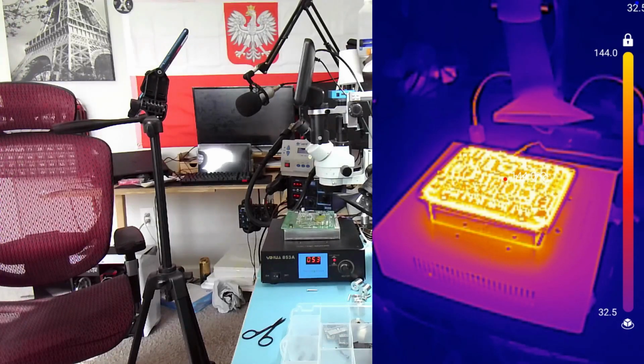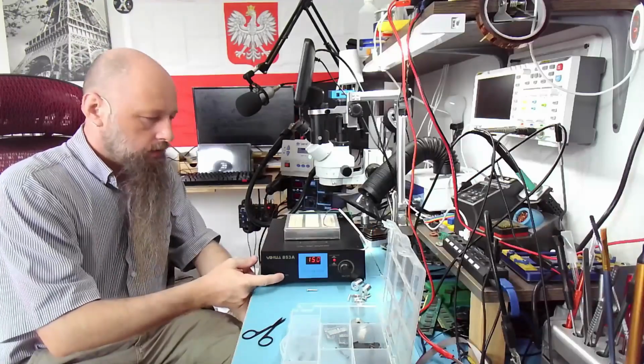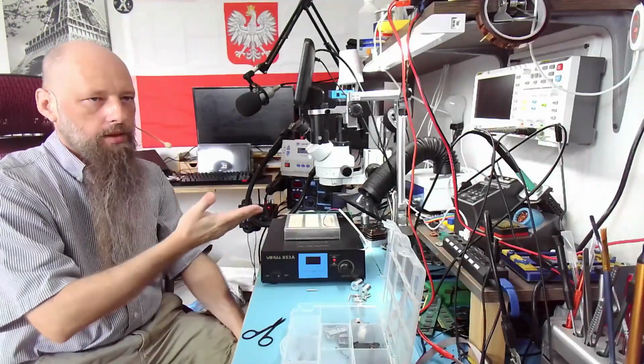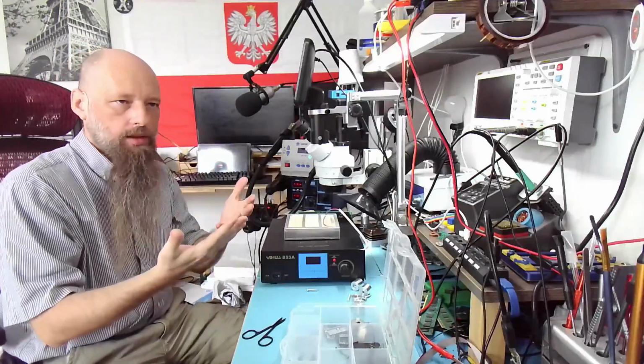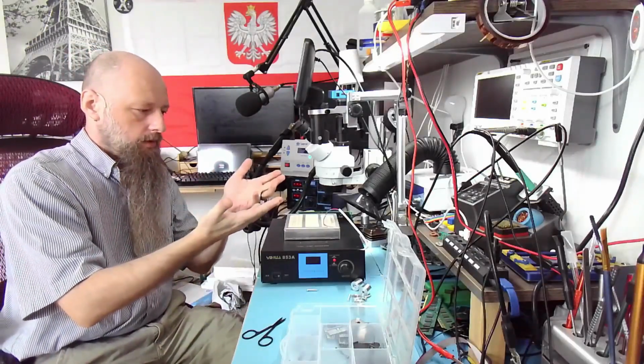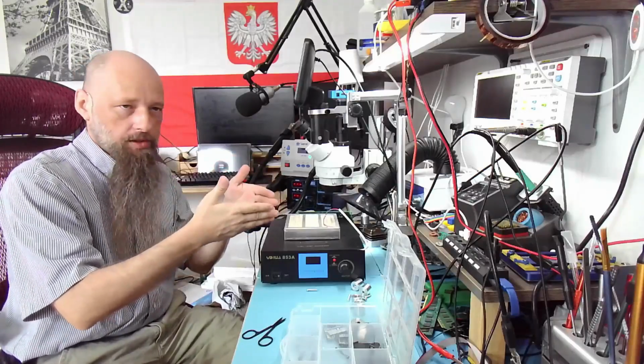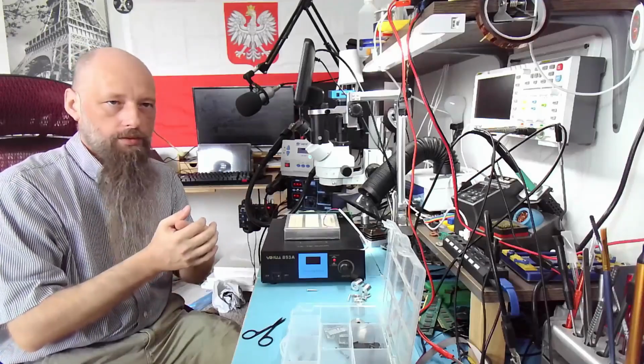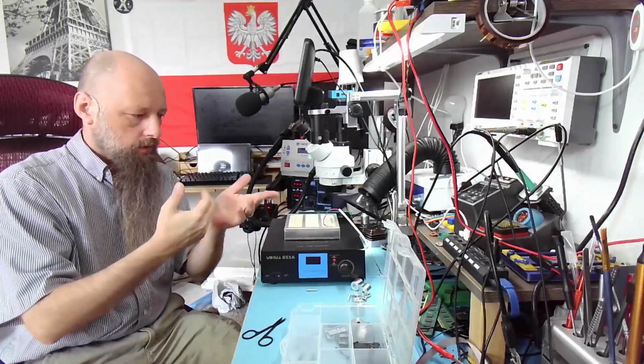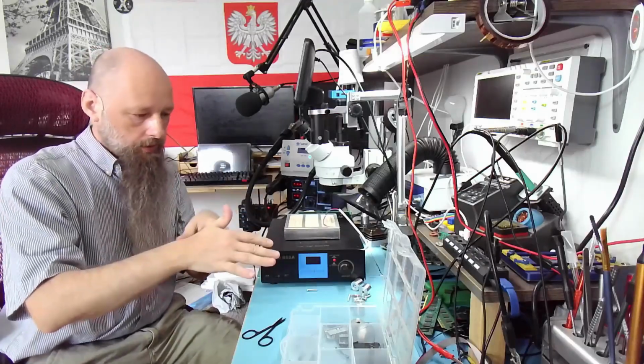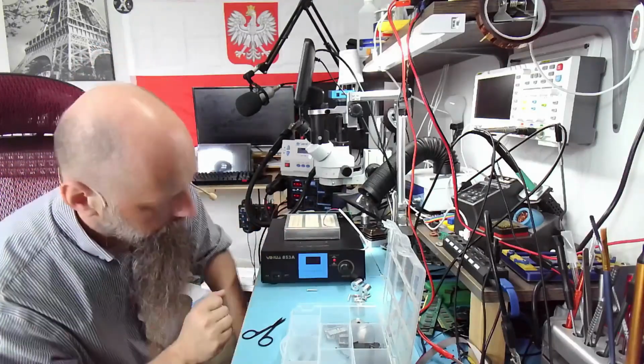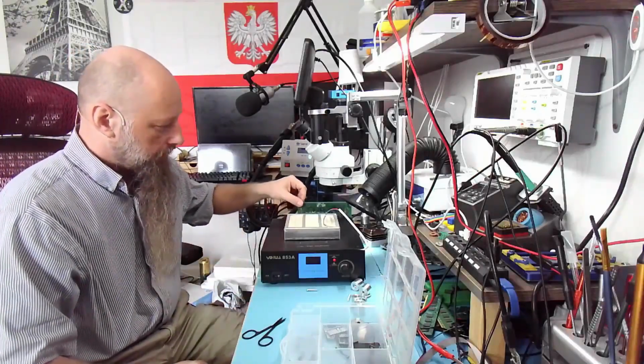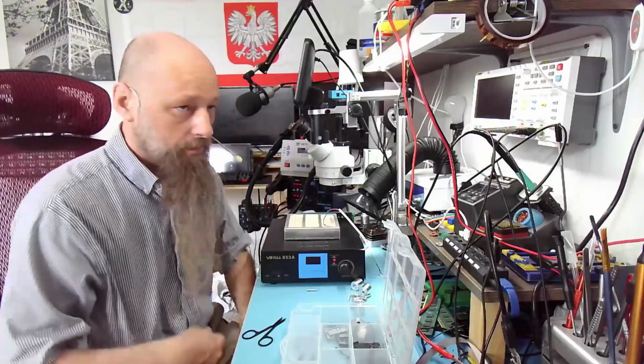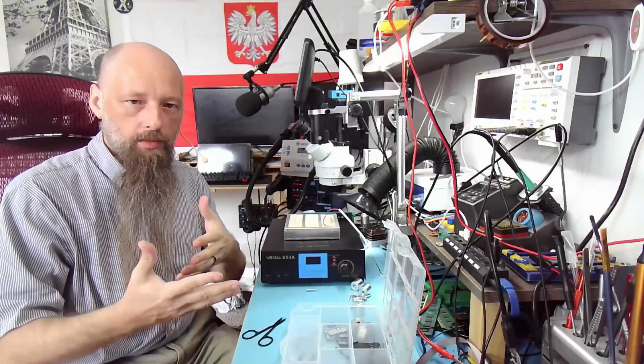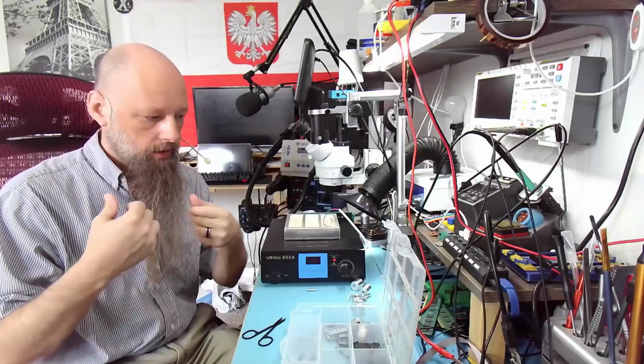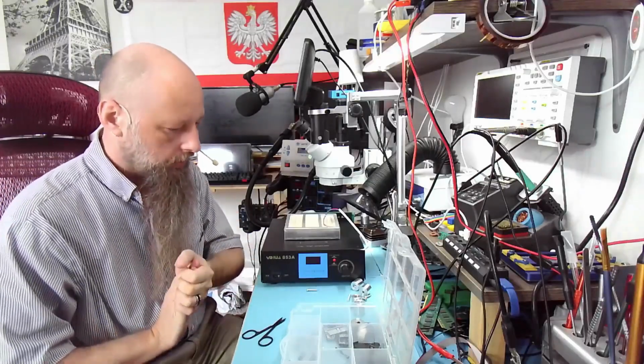and as far as accuracy, I don't see the accuracy here. This is just a matter of calibration, but in this case it's not even a matter of calibration per se. It's not like we're reading wrong. It's the contact that the thermistor has with the surface is not good enough to actually absorb that temperature. So right now we're 50 degrees off. We could account for that with calibration, for sure. But I think the better option is to just replace the thermistor with something a little quicker, something that absorbs temperature faster and doesn't need as great of a contact as this one needs.